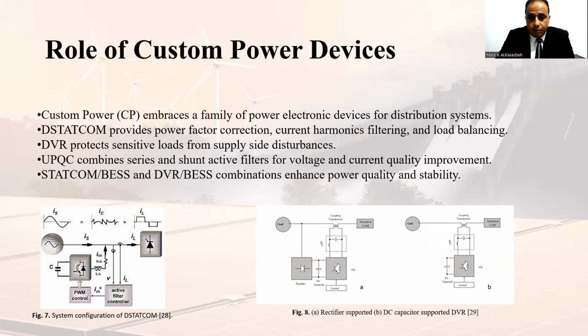Role of custom power devices. Custom power devices embrace a family of power electronics devices for distribution systems. Distribution STATCOM provides power factor correction, current harmonic filtering, and load balancing. DVR protects sensitive loads from supply side disturbances. The unified power quality conditioner combines series and shunt active filters for voltage and current quality improvement. STATCOM or dynamic voltage restorer can be combined with a battery energy storage system, and this combination enhances power quality and stability.